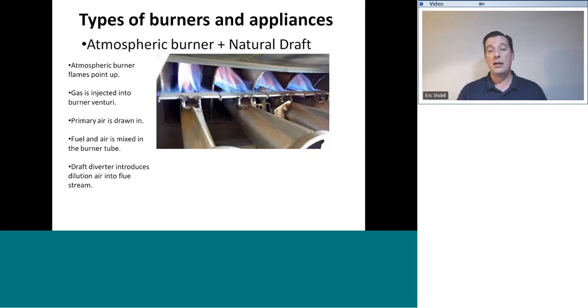But that's not to say that you can't tell something by looking at the flame, and you can. Now, I'm sure you have heard that you want to see a blue flame and that yellow or orange flames are bad. But take a look at this picture, especially this one here on the left. You see a lot of yellow here. You see a lot of yellow and orange here as well, and there's orange here. That's not a bad flame. That's normal. This upper portion of the flame right up here isn't really even considered a part of the flame. The flame that we're concerned with are these little itty-bitty guys down here in the center. And when you're watching the flame, if you look for those small, what I call flame kernels, because they almost look like a kernel of corn sitting on top of the burner, you'll notice that they have a very distinct shape and outline independent of the rest of this corona around the rest of the flame.